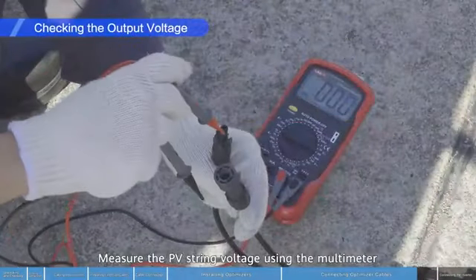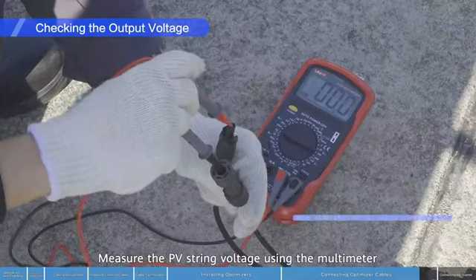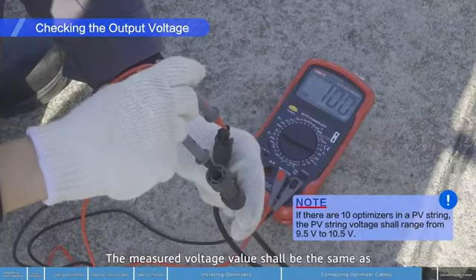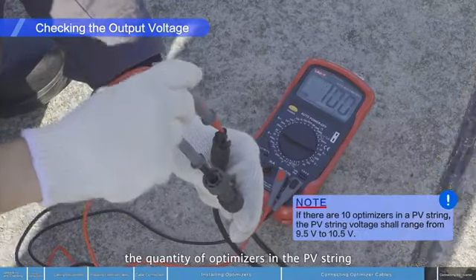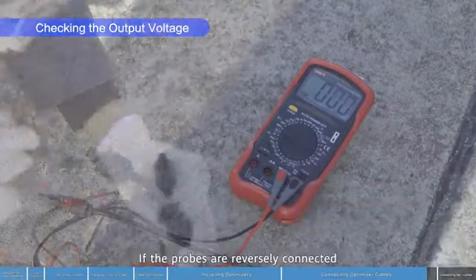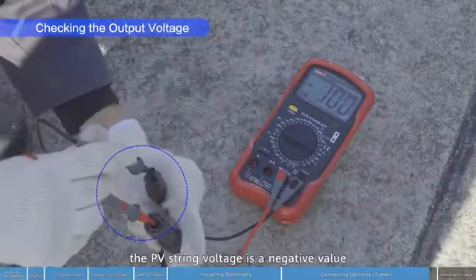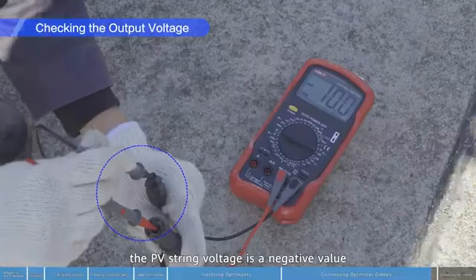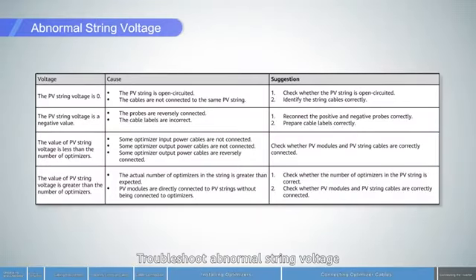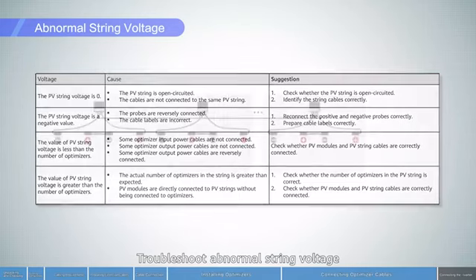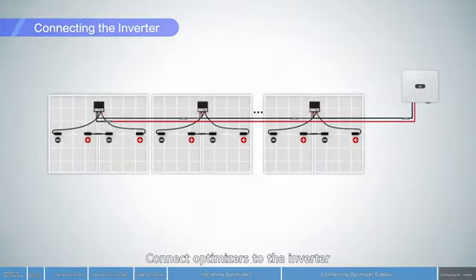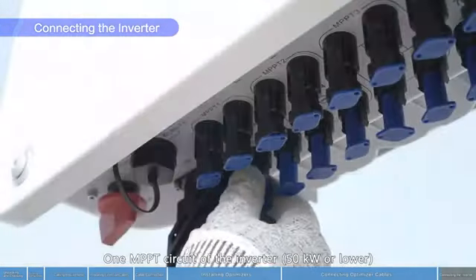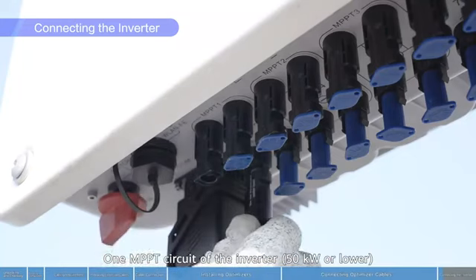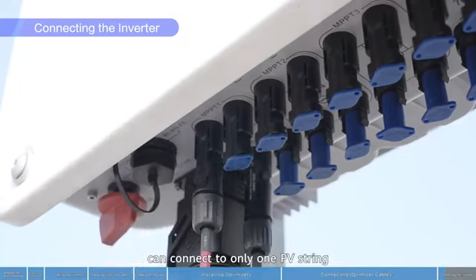Measure the PV string voltage using the multimeter. The measured voltage value shall be the same as the quantity of optimizers in the PV string. If the probes are reversely connected, the PV string voltage is a negative value. Troubleshoot abnormal string voltage. Connect optimizers to the inverter. One MPPT circuit of the inverter, 50 kilowatts or lower, can connect to only one PV string.